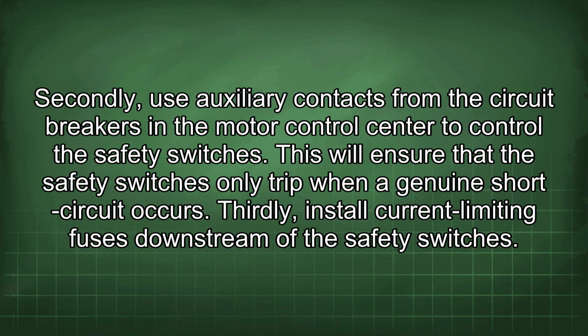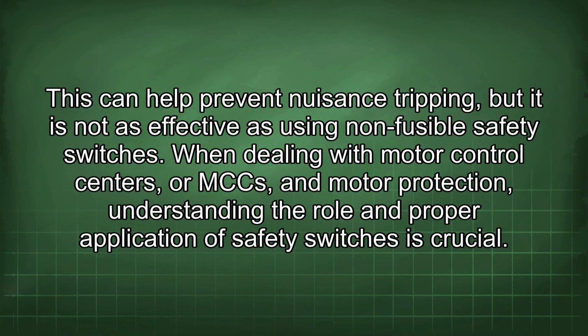Secondly, use auxiliary contacts from the circuit breakers in the motor control center to control the safety switches. This will ensure that the safety switches only trip when a genuine short circuit occurs. Thirdly, install current-limiting fuses downstream of the safety switches. This can help prevent nuisance tripping, but it is not as effective as using non-fusible safety switches.